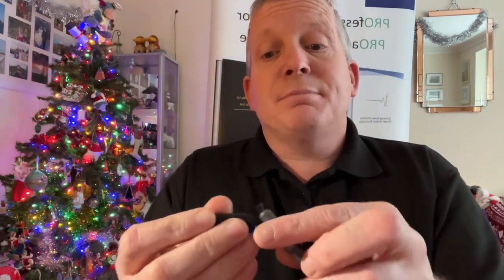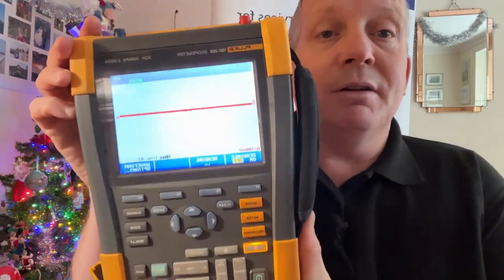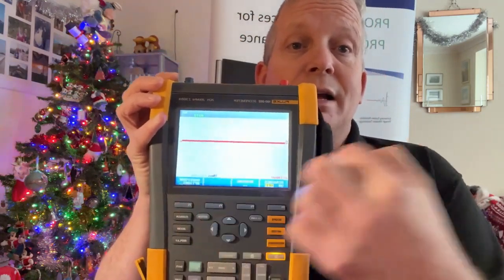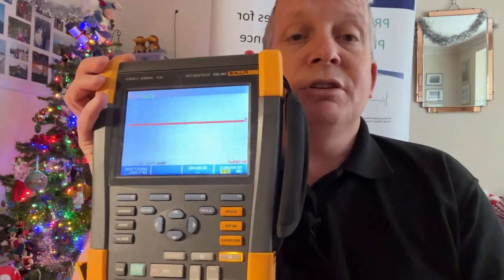And we put on a magnetic stand, start the motor up, and that then makes contact with the shaft, which gets plugged into the scope. And the other end of the scope then goes into the earth. So this is the scope, and what we can actually do is measure and quantify in a waveform the discharges, and it's a super fast scope, so we can pick up those defects really early, and it quantifies it. And there is a rough guidance of how many volts of discharge will give you damage, and some assets you can grease more, technically over grease, but you keep the damage down and you can make it last longer. What we'll do is we'll look at the close-up images of the bearing now.